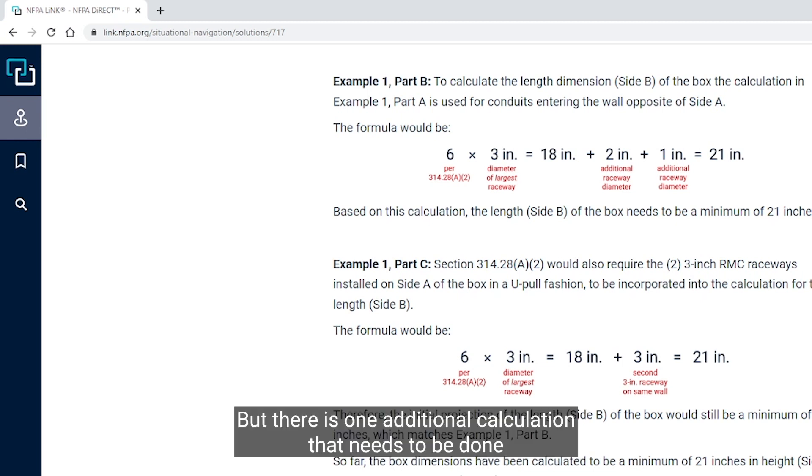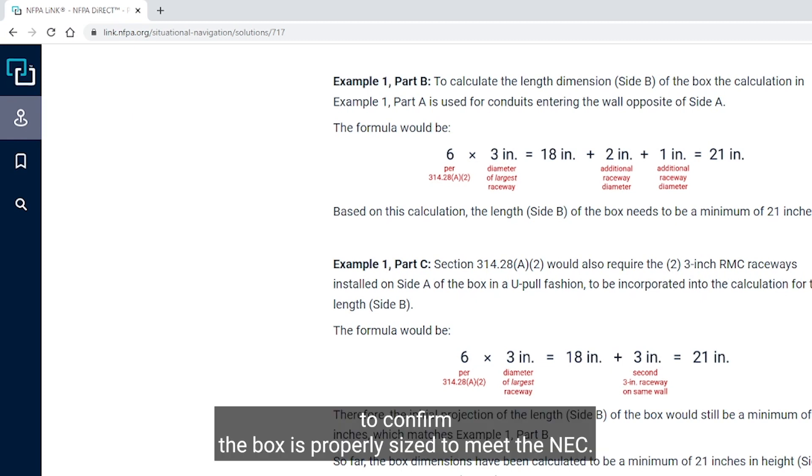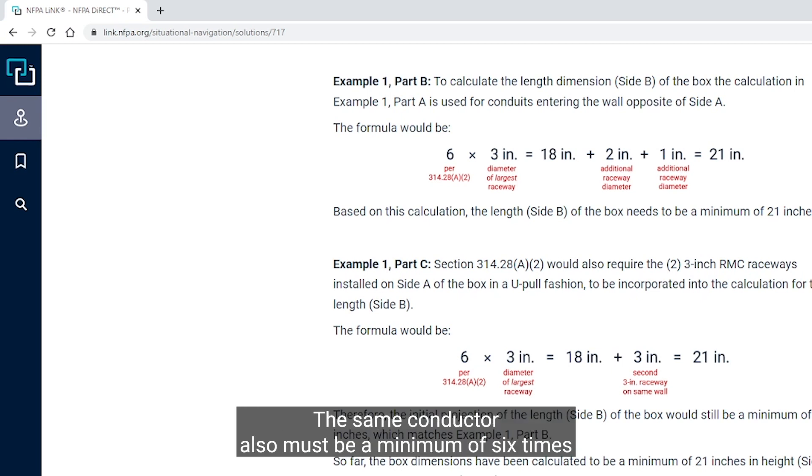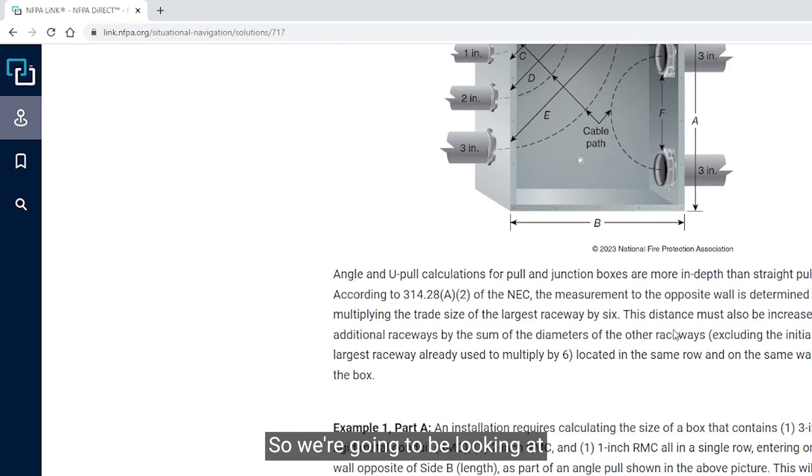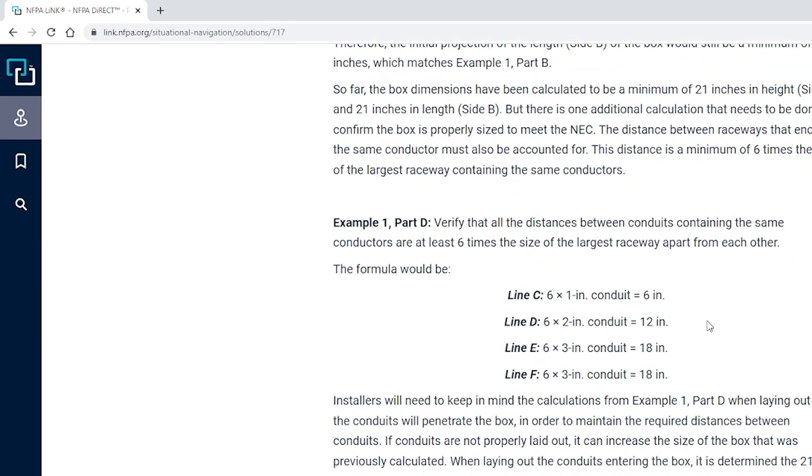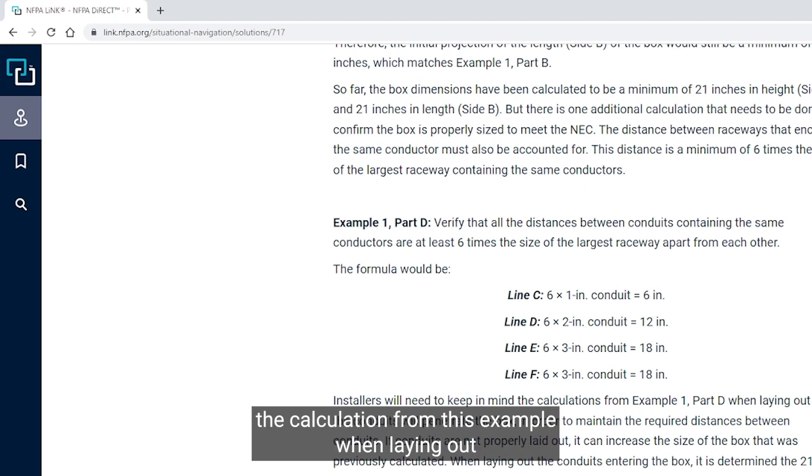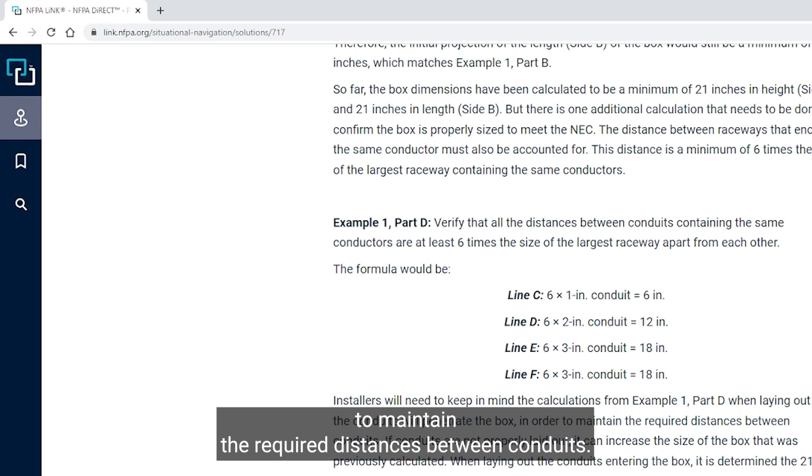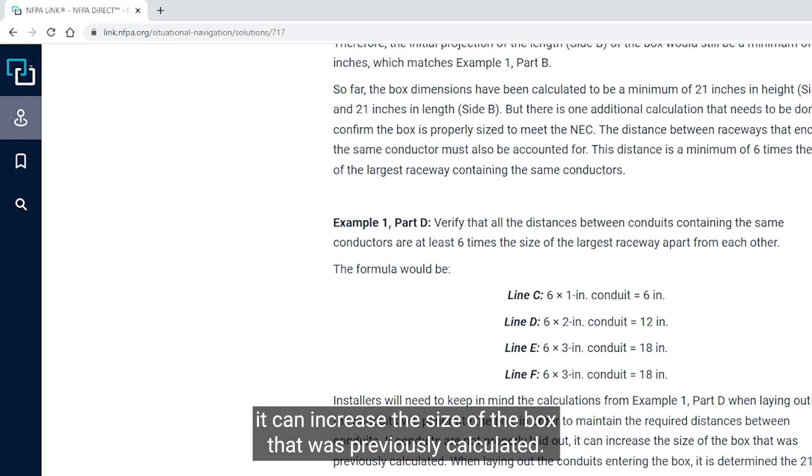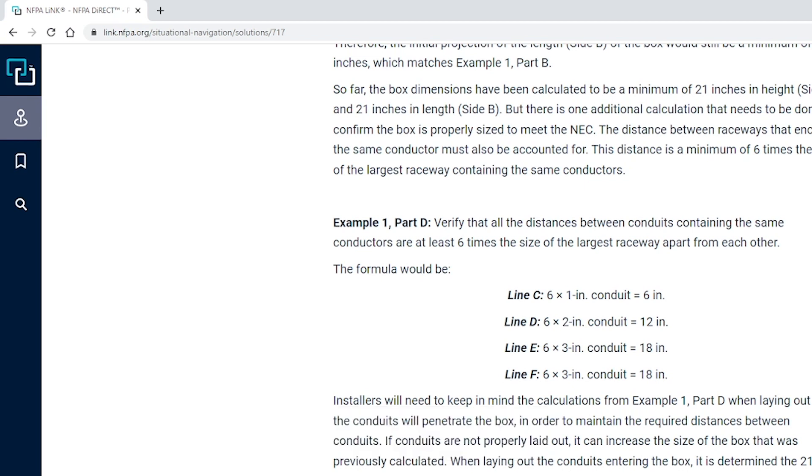According to 314.28(A)(2), we would need to multiply the two 3-inch, one of the two 3-inch raceways on side A by 6. So this formula would be 6 times 3 equals 18 plus the 3-inch is 21. So the wall opposite of A, so that again B dimension would still be 21 inches. So far the calculation of our box has been sized at a minimum of 21 inches in height, side A, and 21 inches in length, side B. But there is one additional calculation that needs to be done to confirm the box is properly sized to meet the NEC. The distance between raceways that enclose the same conductor also must be a minimum of 6 times the size of the largest raceway that contain the same conductors.